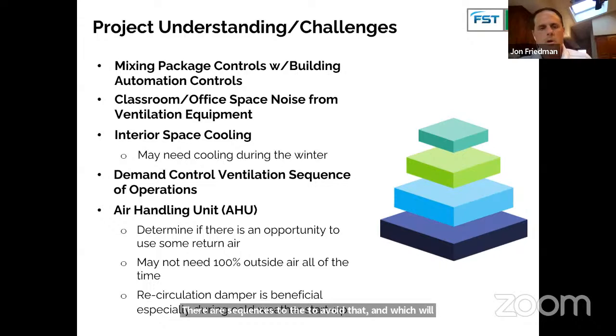With the air handling units, a lot of times we are putting in DOAS units, dedicated outside air system units, and a key thing is at startup on a very cold day, there's no one in the building yet. A lot of them don't have recirculation dampers now, and you're pulling in single digit outside air and you're tripping freeze stats and that kind of thing. If you do have that recirc damper, it's a lot easier to start up that unit in very cold temperatures, and it's just more efficient, period.